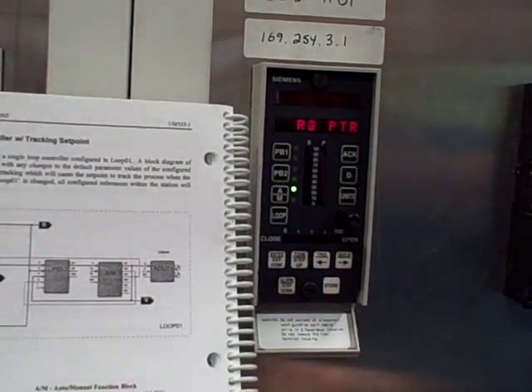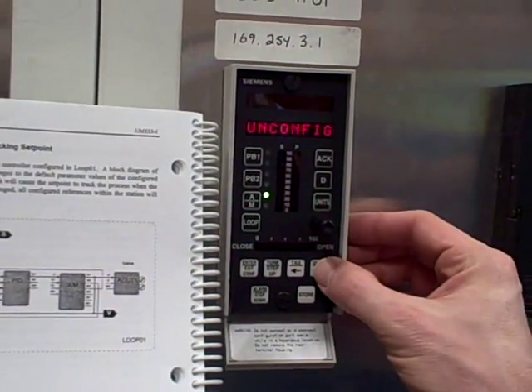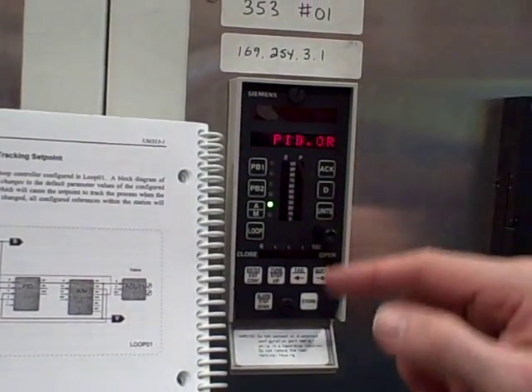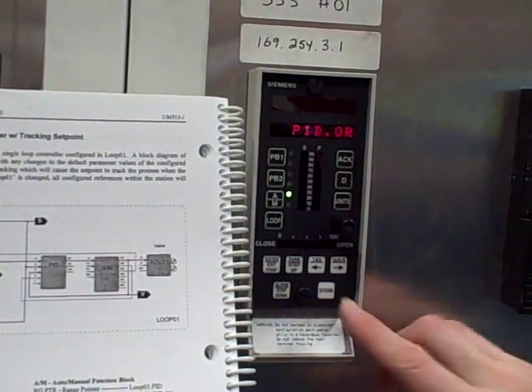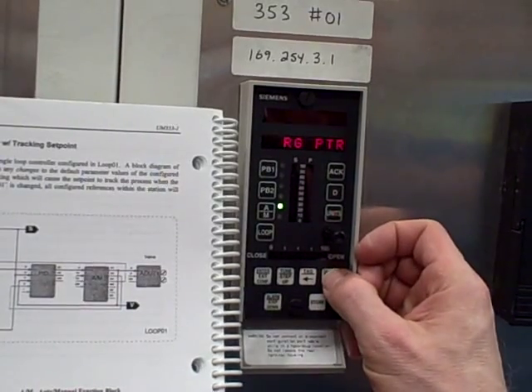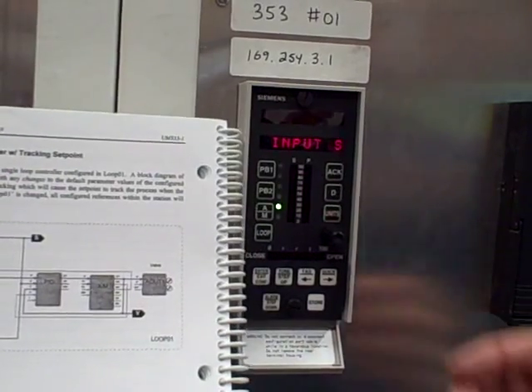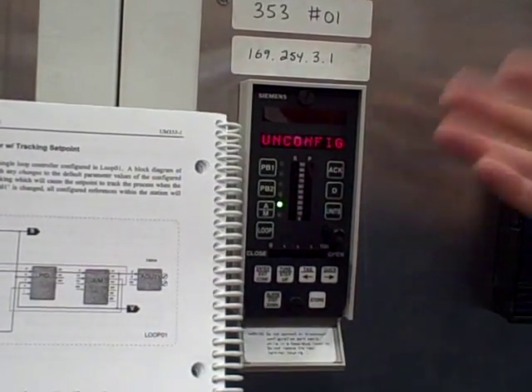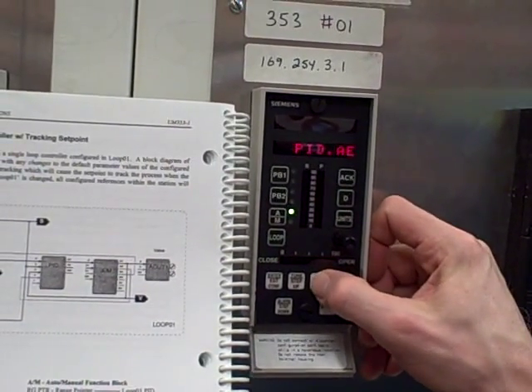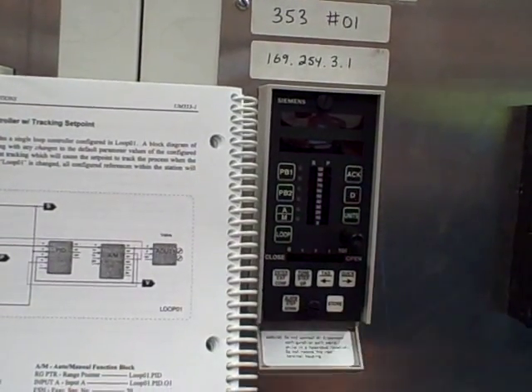Stepping into analog output 2, I go into range pointer. I've got to tell it where it gets its range pointer from. I can select all the available range pointers, and the one that the other analog output block had was PID dot OR, so I'm going to select that one and store. Then stepping up to the next parameter in A out 2, which is its input S — it wants to know where it gets its signal from. Stepping down to that, it's unconfigured. I want to choose auto manual dot 01, same as the other analog output block, and I store that.